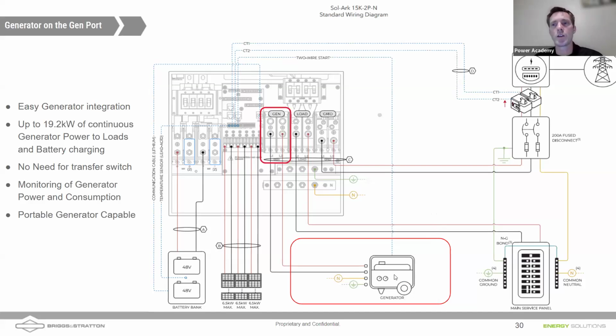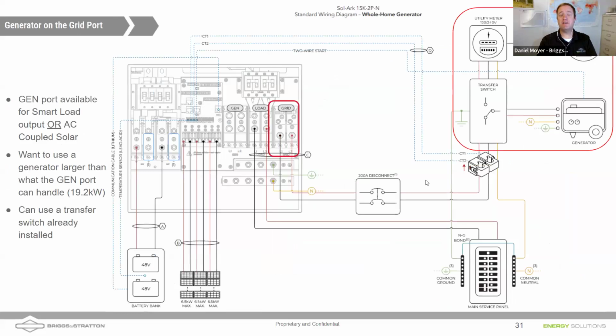So you'll want to use a 2-wire start enabled generator or get an aftermarket 2-wire start enabler. And so that kit, or that generator with the 2-wire start, would allow you to just run off your batteries till the batteries get low before starting that generator. Save fuel, save wear and tear on the engine, right? Use that 2-wire start.